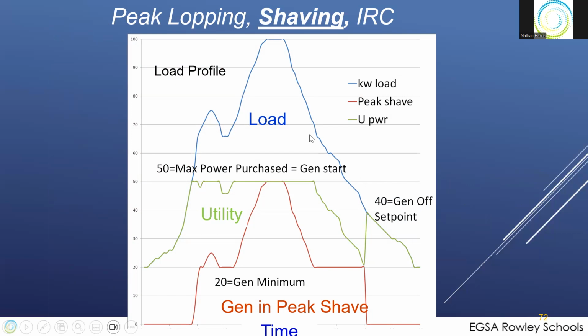Okay, we're doing okay. So let's talk about peak lopping, peak shaving, and IRC. These are different terms that we use to share the load between the utility and the local generation. Again, your concept is a generator feeding the load, a load bus tied to utility. So utility, load, generator. Your load profile, which you should have whenever you're doing a system development, will say what I expect my load profile to be throughout the day. This is time across the bottom axis. It got cut off a little bit, but this is midnight to midnight, peaking out in the middle of the day. And again, these are made up numbers, but it illustrates the point.